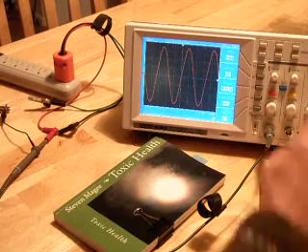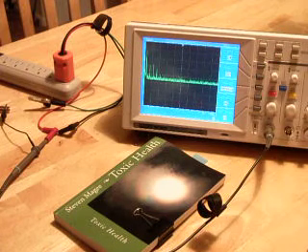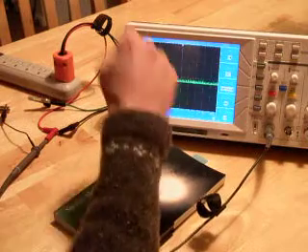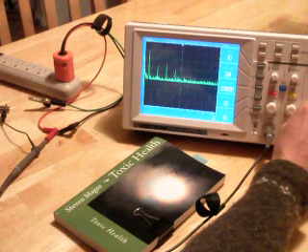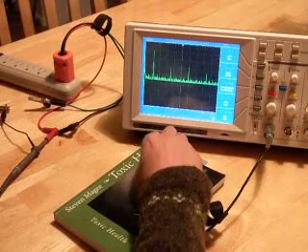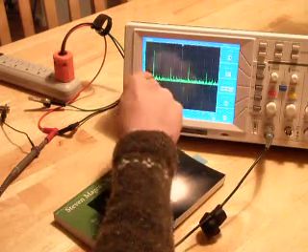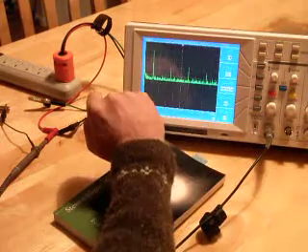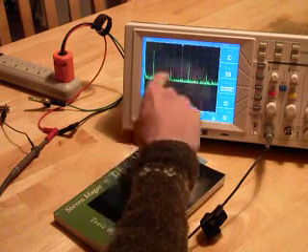I'm going to switch that on right now. So we're on 250 Hz per division. As you can see over on this side, we've got some spikes, so I'm going to expand it out a little bit. Now we're on 50 Hz per division. We can see the fundamental frequency, which is 60 Hz — this spike here — and that is normal. Now these here are what's known as harmonics, and they really shouldn't be there. They're a characteristic of electronic systems and electronic power generation.